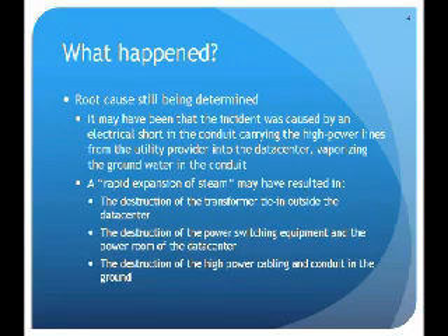It may have been that the incident was caused by an electrical short in the conduit carrying the high power lines from the utility provider into the data center, vaporizing the groundwater in the conduit. I don't know how many of you are familiar with when you run conduit through the ground, you'll typically get some groundwater in there through seepage. Over time, it'll just kind of get in there.